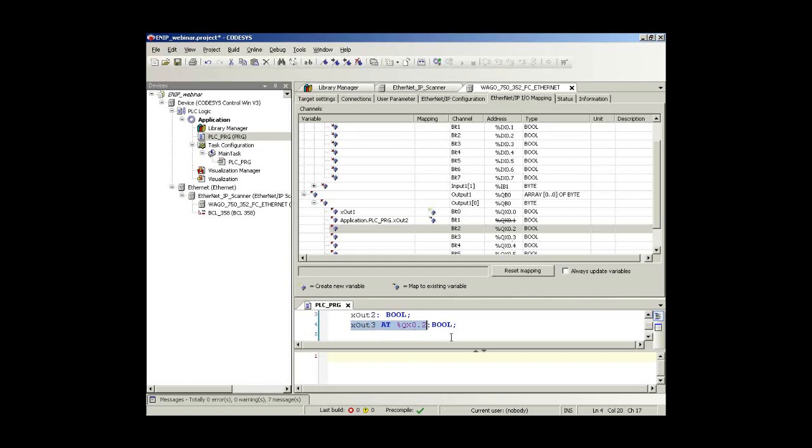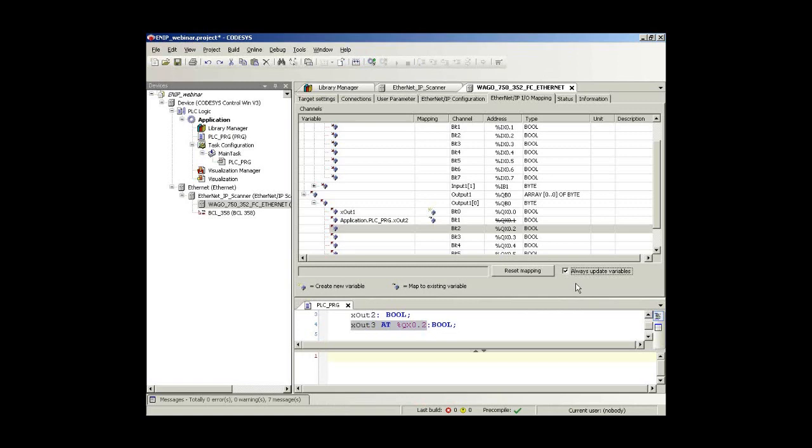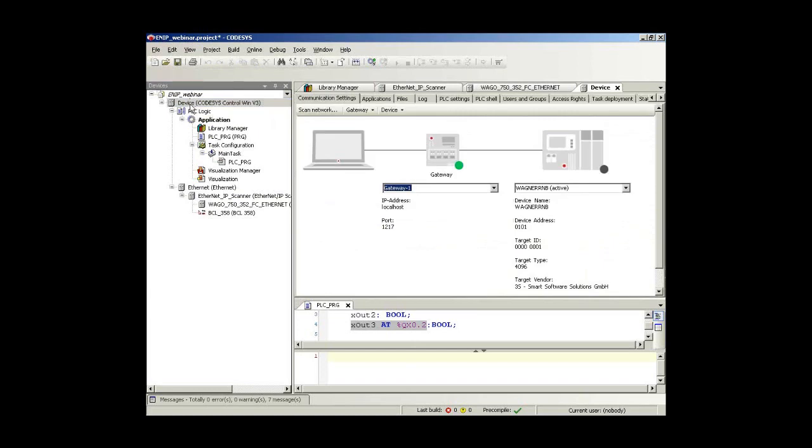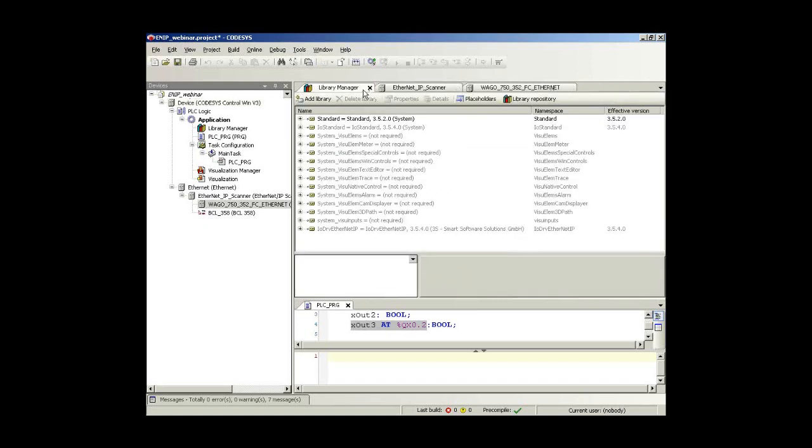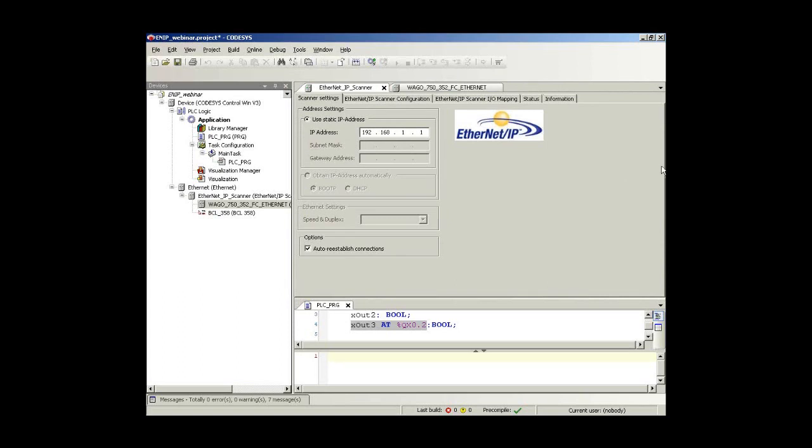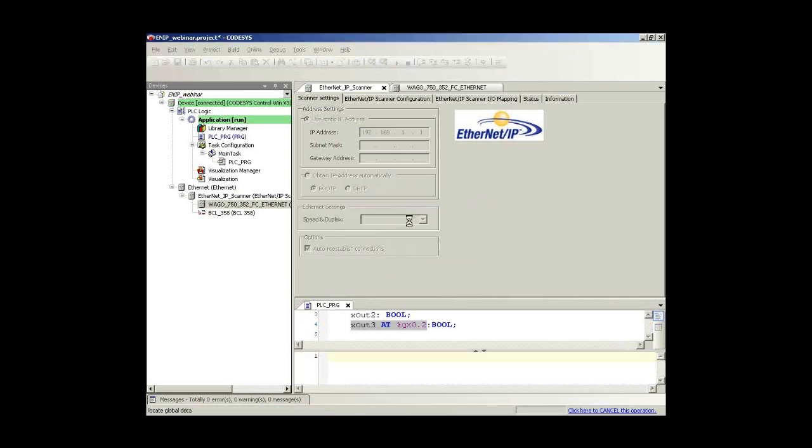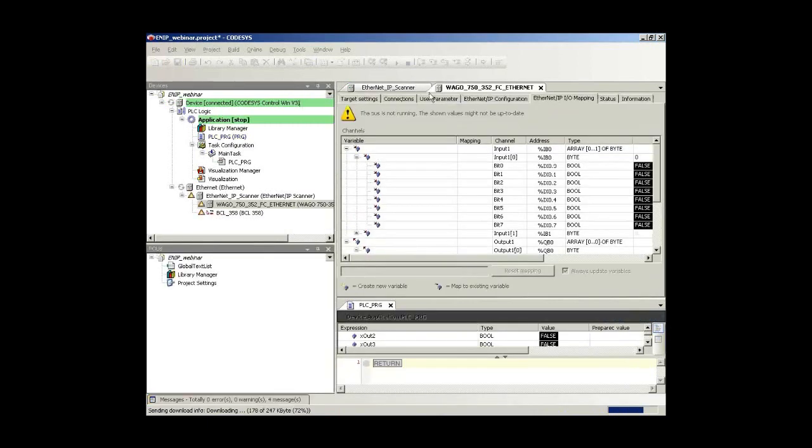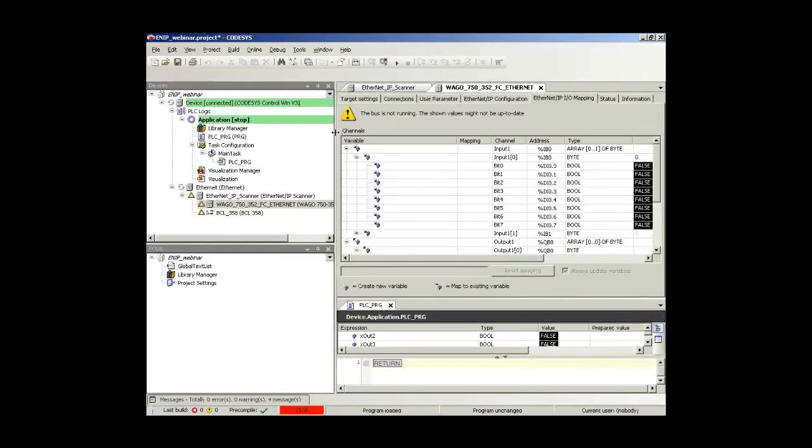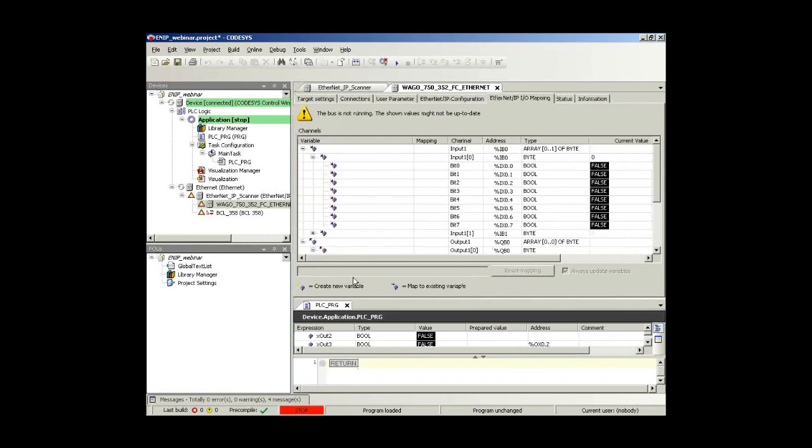Now we have configured everything. I check that box always updates variables because there is no application running so far, then we will be sure we can check that without any code below here. The only thing I need to do is now to connect my device here to the soft PLC I am running on my PC. This is done with the communication dialogue and now I can login. In order to do so I switch here the login or press the login button. The whole stack is now compiled and linked to the application. We see that we have an error message here. The bus is not running, so we have a certain diagnosis in here. But the EtherNet/IP scanner is not yet running. This is because we are still in stop mode.